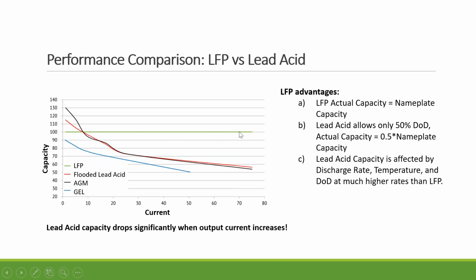With the lithium, you don't have that concern as long as it's within the BMS threshold, like maximum discharging rate. You can expect the battery to last 2 hours. It will not die earlier, and that's also nice, more predictable. Plus, we talk about LFP capacity being your actual nameplate capacity. So for 360 amp hour, you can really get 360 amp hour out of it. With lead acid, usually it's 50%. So when you do a cost calculation, you have to consider that difference. If you want lead acid at 400 amp hour, with lithium you probably need 200 amp hour, maybe 240 amp hour at 80% depth of discharge, as an example.